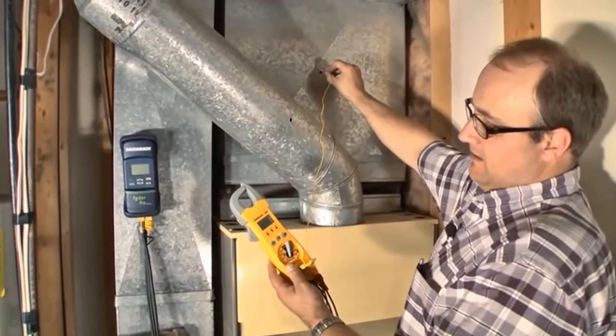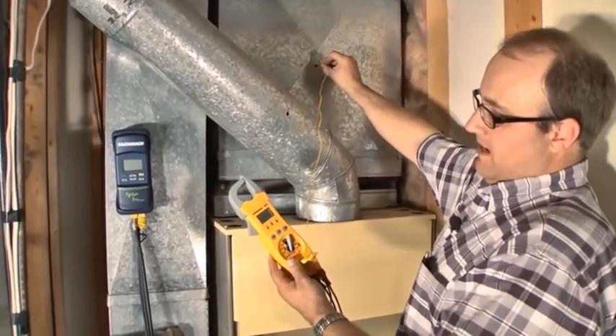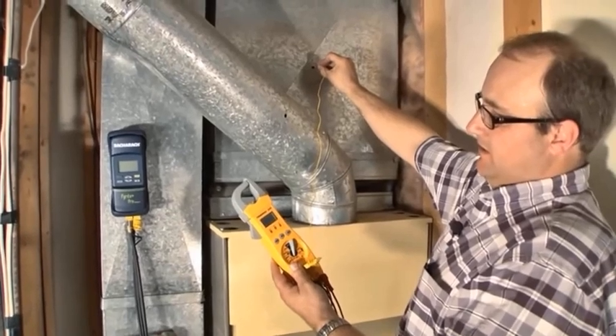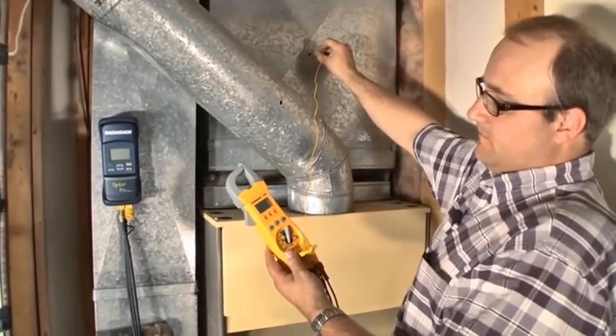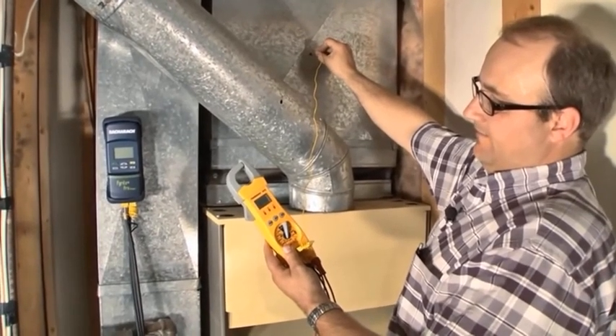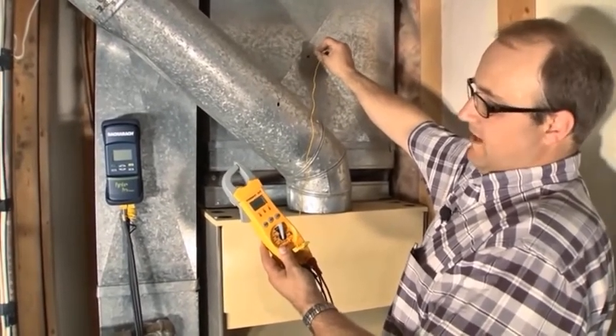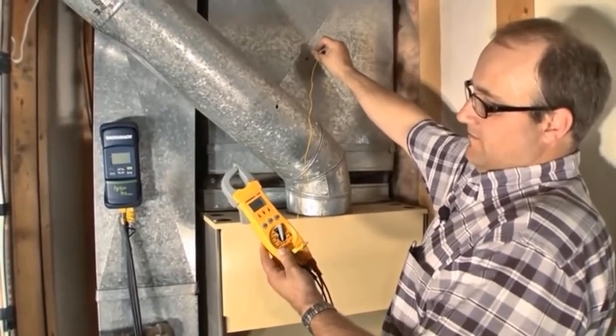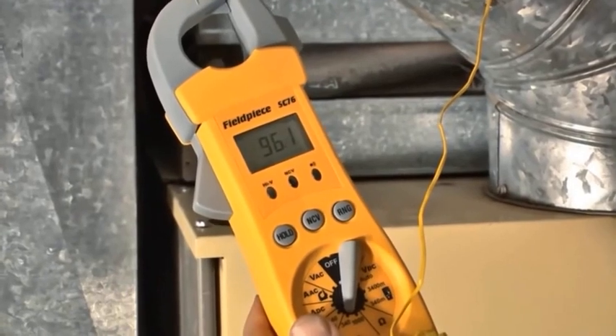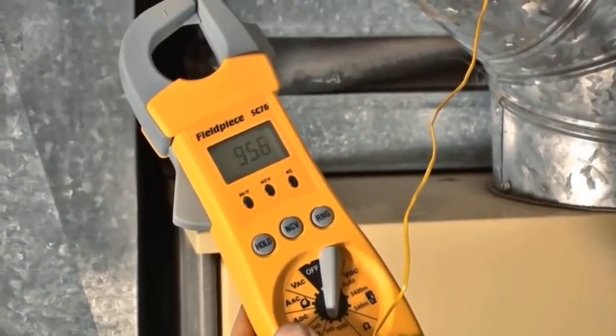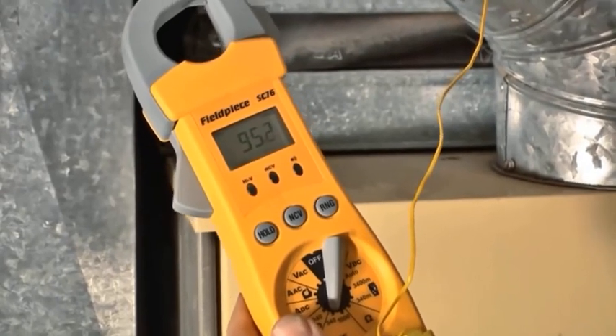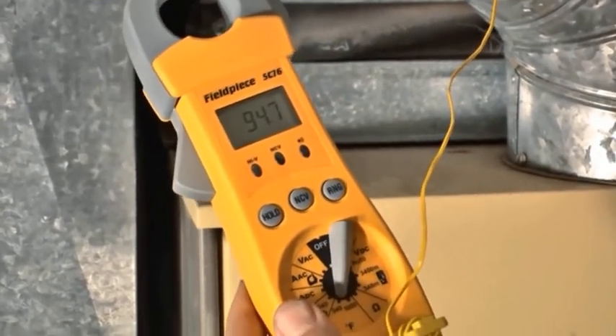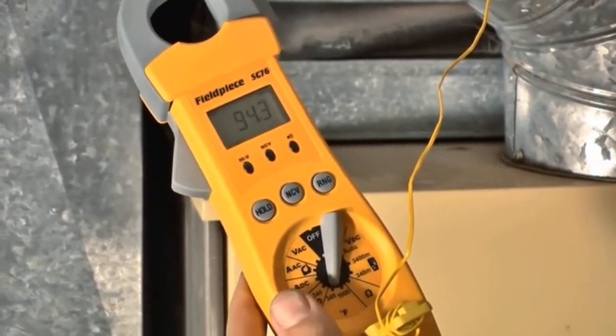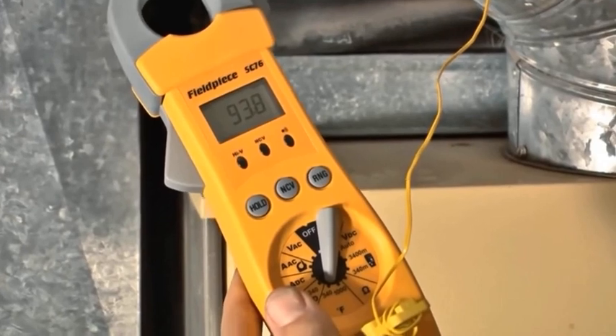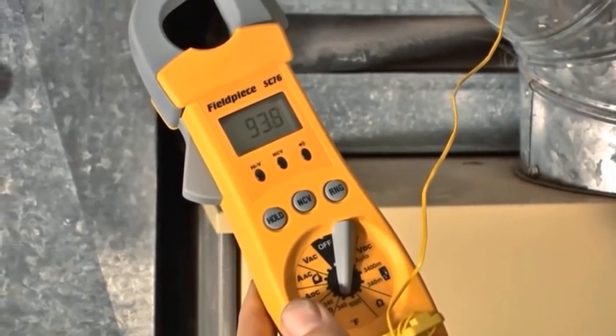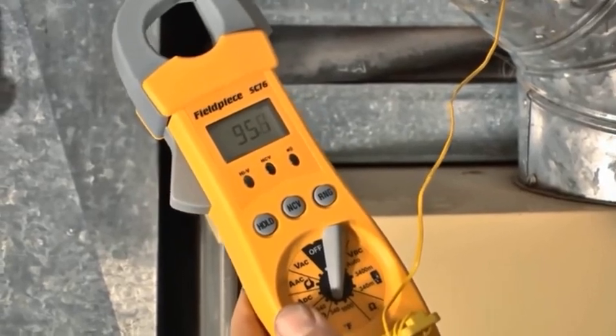I have a sneaky suspicion that the heat exchanger may have a crack in it based on the high parts per million I was getting. So I'm really going to spend a lot of time looking to see if there's a crack in this thing. But we'll get this fan off temperature here first. So the temperature's dropping. That fan's pulling the remainder of the heat out of the heat exchanger, delivering it to the house. No sense in leaving that heat energy sitting in the furnace. And there we go, 90, 93 and a half, 94 degrees. That fan turned off.